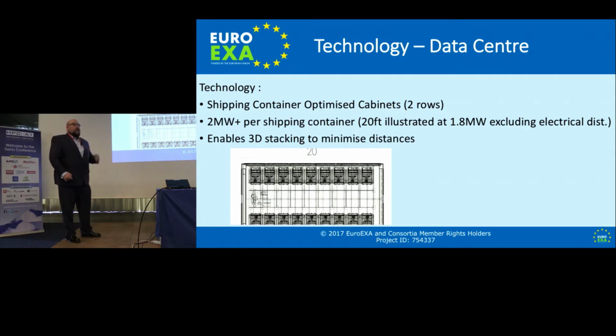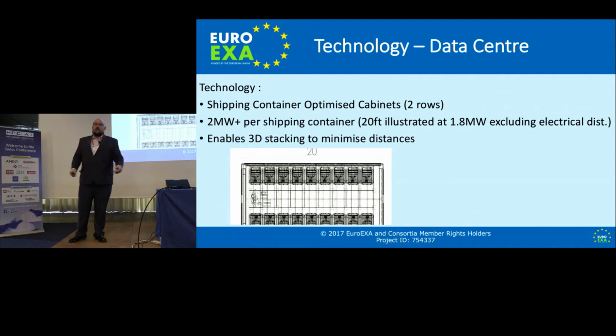So now trying to pack all of this in, we've got to start thinking 3-dimensionally. It's no good for us to think one or 2-dimensionally and lay things out on a single floor, because what we want to do is reduce the distance from one side of the system to the other, minimize that distance. We minimize the distance of transit of the data, that reduces the energy consumption in the chips, and we also reduce the latency, which improves the efficiency of the applications running across it. So we set ourselves the target around 35 to 40 meters from one side of the 60 megawatt supercomputer to the other.